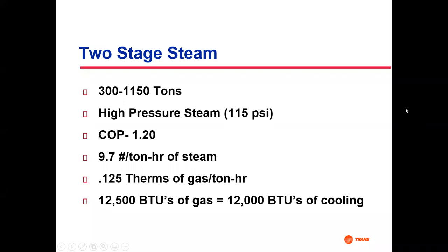Okay, COP. Now we're above 1.2. That says for every unit of costly energy input, I get 1.2 units of refrigeration in whatever unit you want to use, because COP is dimensionless. You put the same unit on top and bottom, they cancel. So it's just the ratio. Well, it's not 6, but it's better than 0.67, so that's what that extra stage gets you.